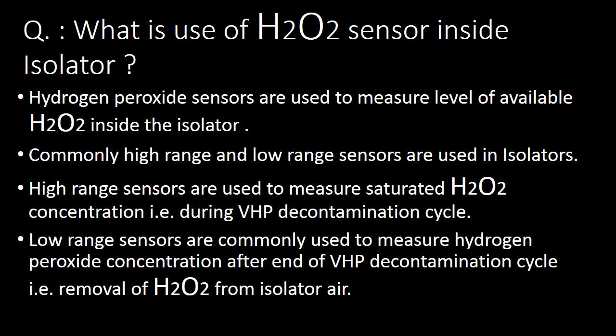Next important question: what is the use of H2O2 or hydrogen peroxide sensors inside the isolator? Hydrogen peroxide sensors are used to measure the level of available hydrogen peroxide inside the isolator. High-range sensors measure the saturated hydrogen peroxide concentration during the VHP decontamination cycle. Low-range sensors measure hydrogen peroxide concentration after the end of the VHP decontamination cycle — that is, during removal of hydrogen peroxide from the isolator air.